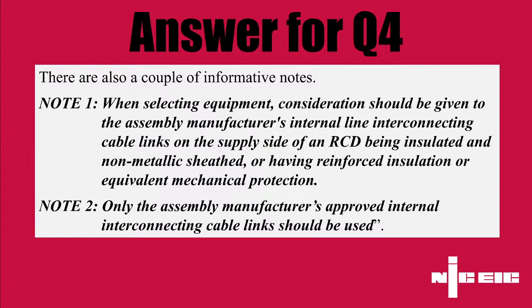What do you think to that, Dan? Yeah, it all comes down to if it's extraneous or not. If it's extraneous, you need to do it regardless, and if it's not, then you don't. It's not really about the regulation changing over, is it? It's about, is it extraneous? And I've referred to probably 314.16. Again, whenever you do additions, alterations, etc., make sure that the existing arrangements are adequate. So for me, forget about if it's on the 17th or 18th, it all comes down to, is it extraneous or not?